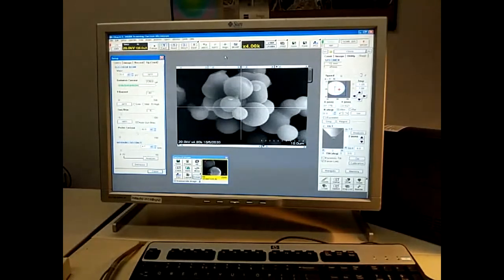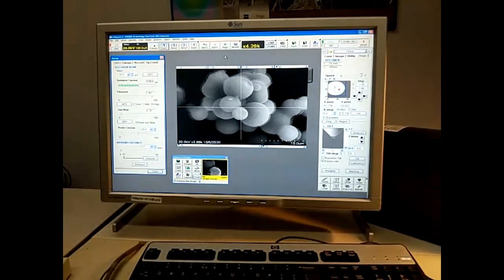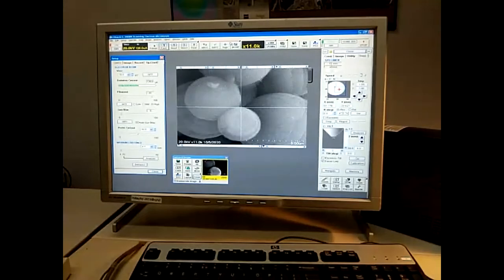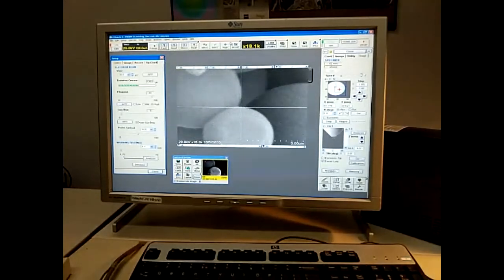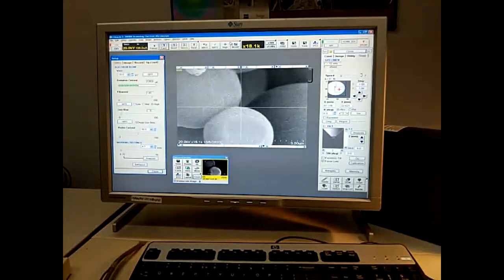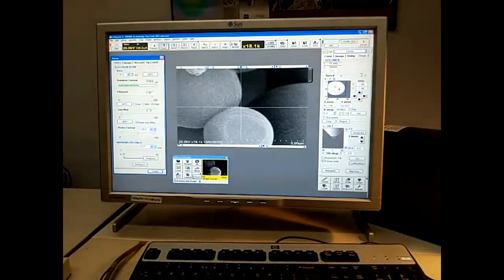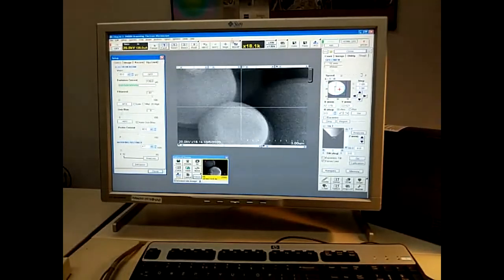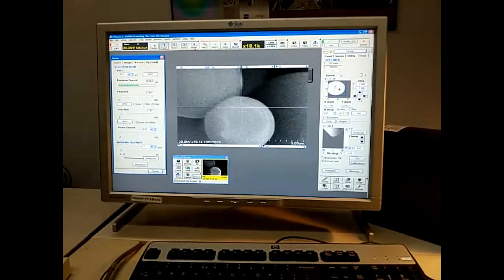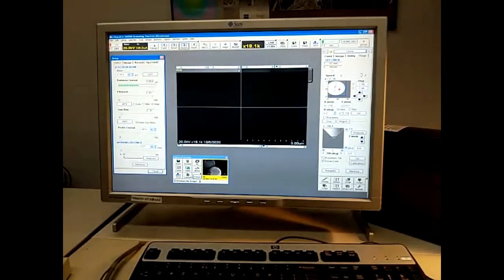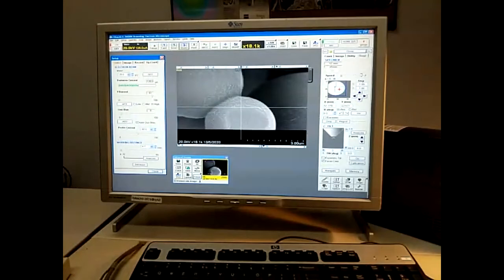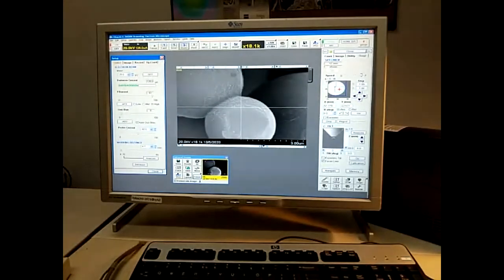Taking that back up. Adjusting focus and contrast to bring out those features again. Put it back in slow mode. We're back up around 20,000.